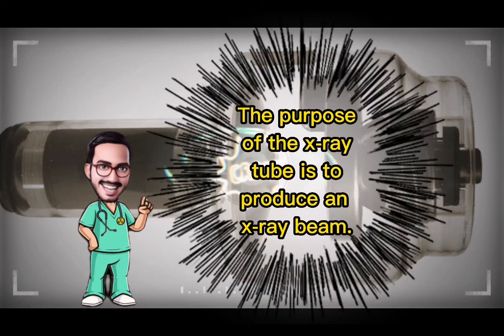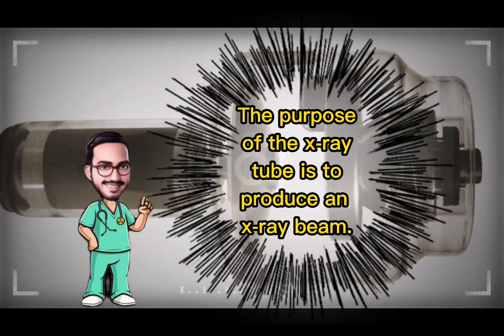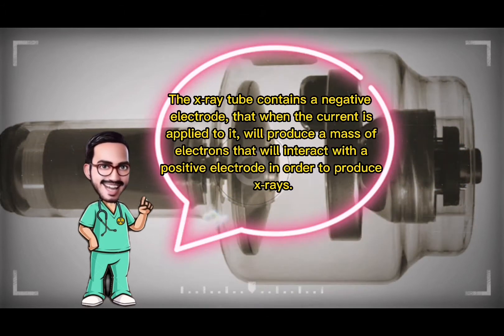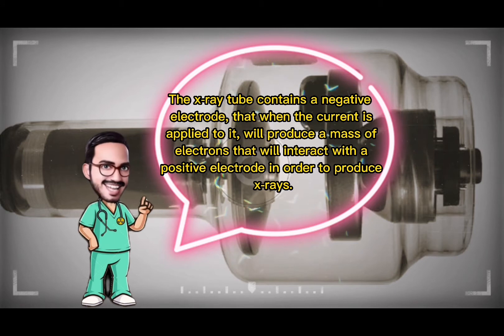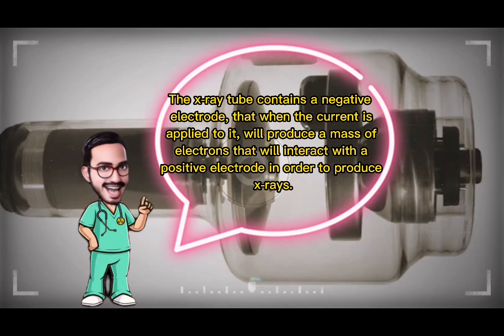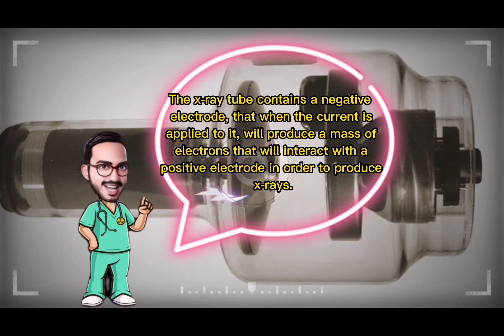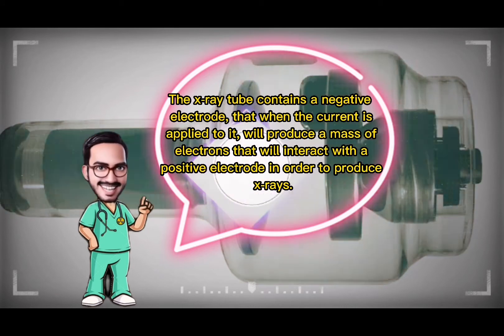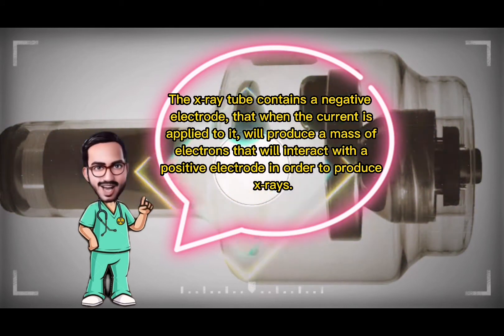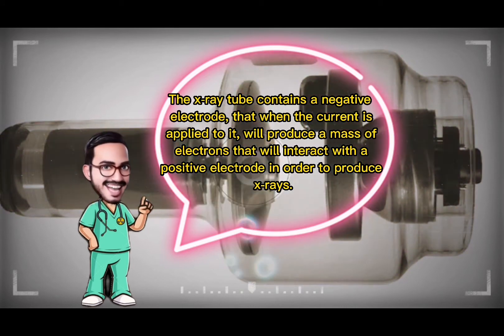The purpose of the x-ray tube is to produce an x-ray beam. The x-ray tube contains a negative electrode that, when current is applied to it, will produce a mass of electrons that will interact with the positive electrode in order to produce x-rays.